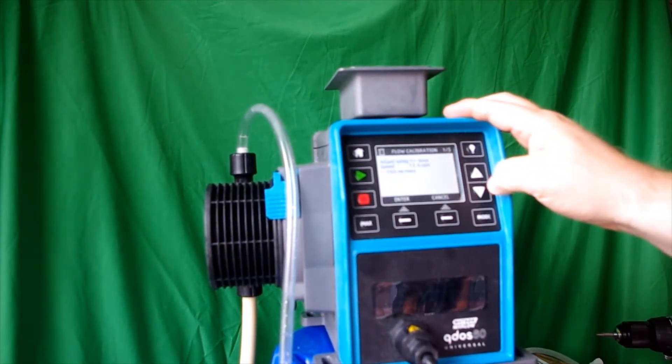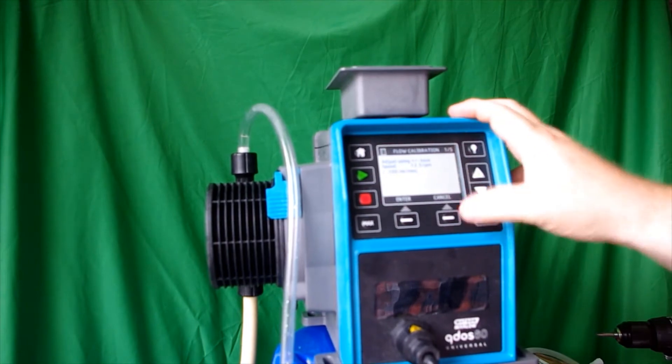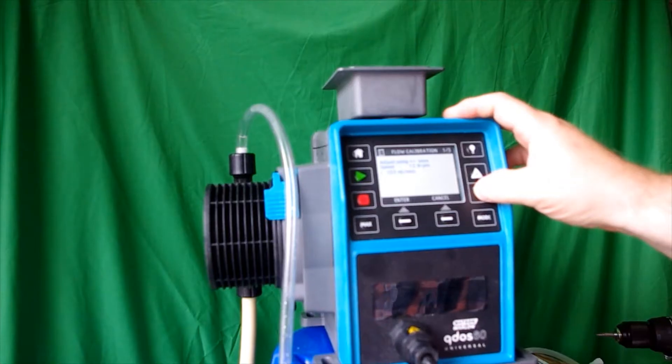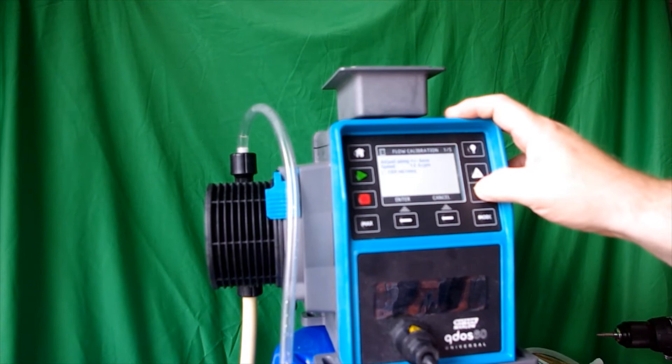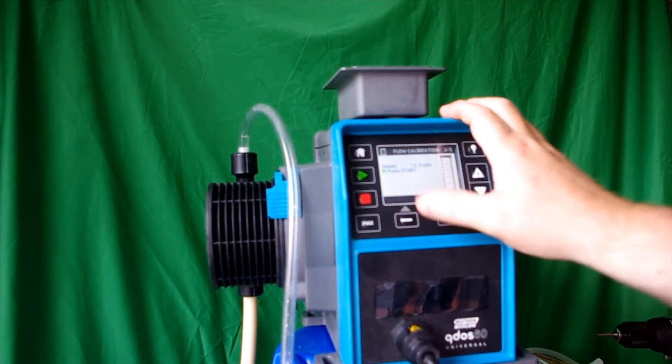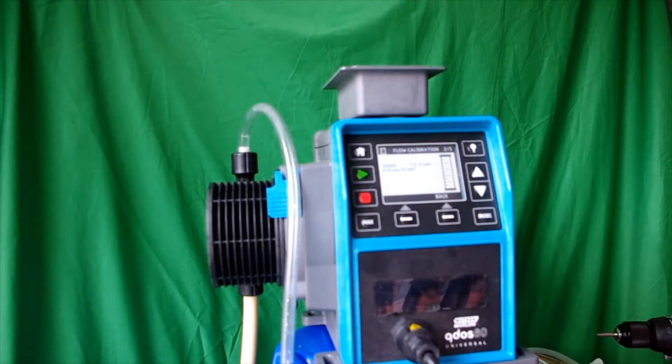If you wanted to adjust it, you use your up and down arrow key to get you within 10 or 15 percent of your average flow rate and press enter. Now it says get ready to go, get your calibration column, your graduated cylinder ready to go, get your stopwatch ready to go and zero it out if you want to use a stopwatch.